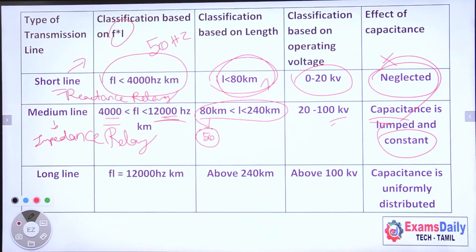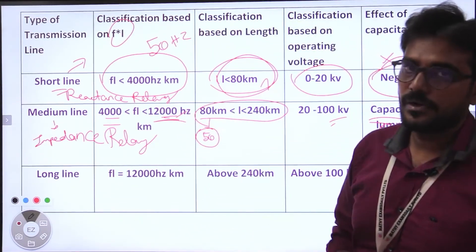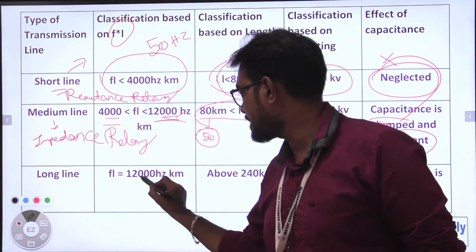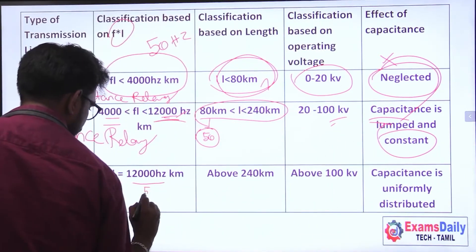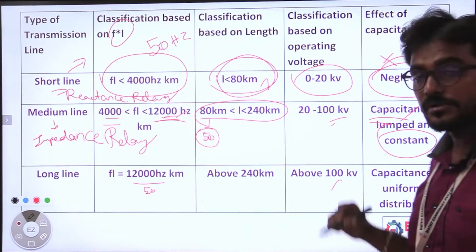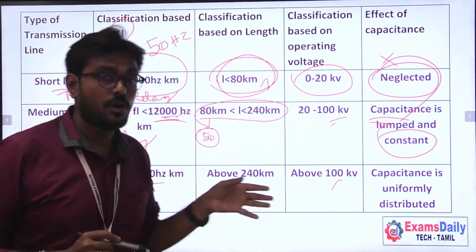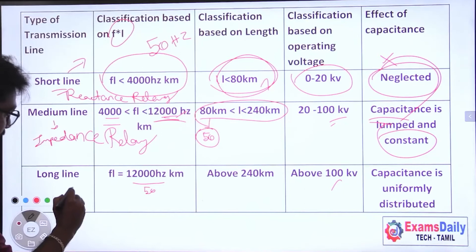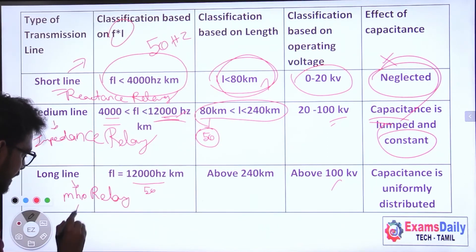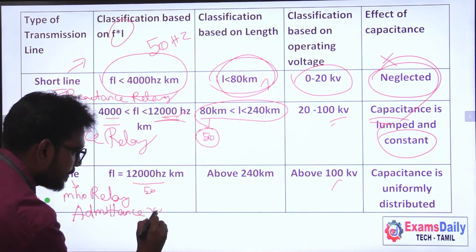For the long transmission line, the frequency-length product is more than 12,000. The length is above 240 km, and the operating voltage is above 100 kV. In a long transmission line, capacitance is uniformly distributed. The relay used for long transmission line is the mho relay, also called the admittance relay.